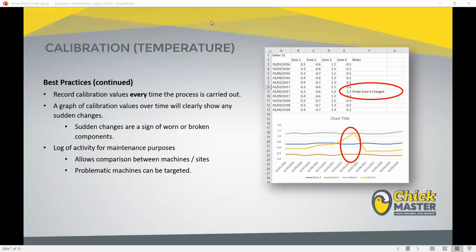But what you're after is a known good reference point that can sit in a cupboard, send it to an external company just to verify that it's good. And that's your Bible in effect. That's your known good point that you then use to calibrate your calibration box. And then once you've got consistency and reliability with your calibration box, you can use that on the rest of your incubators. Very good. All right, Craig, go ahead and move us forward.